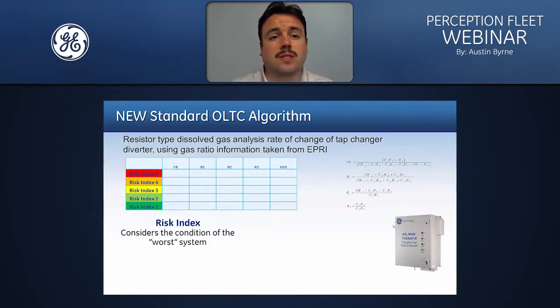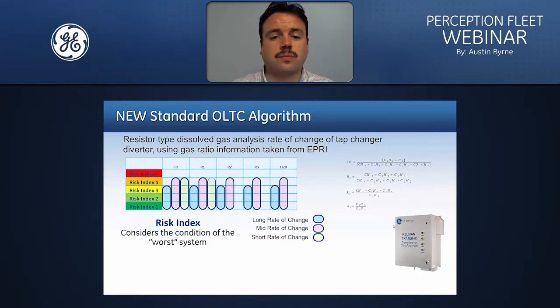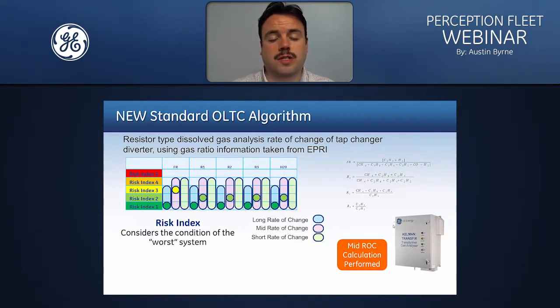We also have the standard OLTC algorithm in terms of rate of change of gases. So not only do we look at the ratio for concentration, we also look at the gas rate of change. You can see it follows the same principle as the standard DGA algorithm for rate of change. So we look at the ratios again, the 4 ratios and moisture. We perform a long rate of change calculation for the ratio, we perform the mid rate of change calculation, and then we perform a short rate of change calculation.